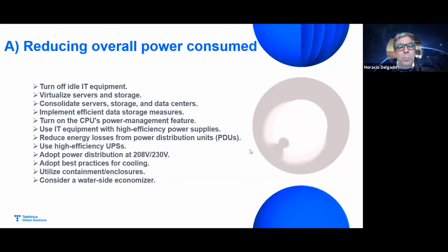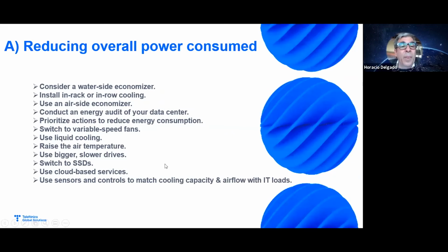There are several best practices for cooling that can also be implemented to lower the power consumption of data centers. Among those, some of the things for cooling is to use containment enclosures that can trap or direct hot air, basically manage hot and cold air in better ways, and installing in-rack or in-row cooling.